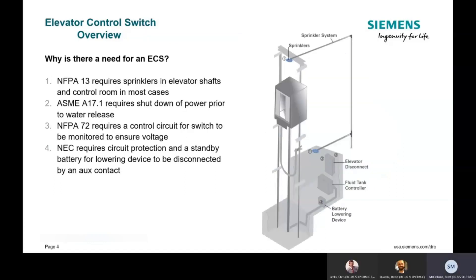Here's a diagram that shows a typical layout of an elevator shaft and where the components would be within that shaft. I'd like to talk about how the different components communicate with each other and the order in which this switch operates. The first thing that's going to happen during a fire event is a fire detection device, like a smoke detector, will send a signal to the fire alarm control panel. Next, that fire alarm control panel will then trigger the fire alarm, contact the fire department, and return the elevator to the ground floor. Once the elevator reaches the ground floor, the doors will open and allow passengers to depart.